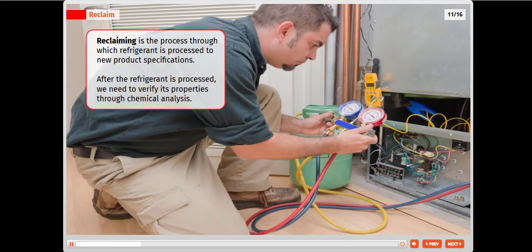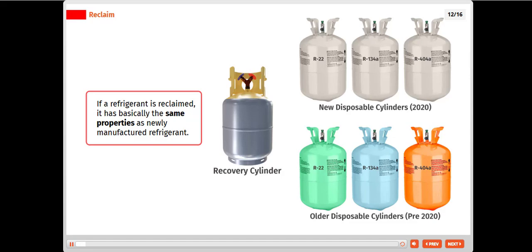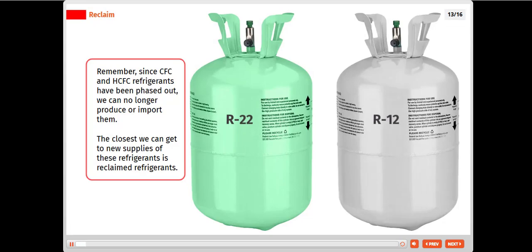Reclaiming is the process through which refrigerant is processed to new product specifications. After the refrigerant is processed, we need to verify its properties through chemical analysis. If a refrigerant is reclaimed, it has basically the same properties as newly manufactured refrigerant. Remember, since CFC and HCFC refrigerants have been phased out, we can no longer produce or import them. The closest we can get to new supplies of these refrigerants is reclaimed refrigerants.